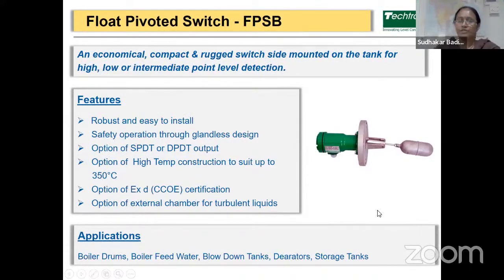The next one is a float pivoted switch. This is a single point switch, which is economical, compact, and rugged. It is side mounted to the tank for level detection at high, low, or intermediate level. This is robust and very easy to install through the flange or screw flange connection. The switching operation is safe through a glandless design. The switching output can be available as SPDT contacts or DPDT contacts. The option of high temperature construction is available, which suits up to 350 degrees Celsius. The option of X-proof enclosures, that is CCOE certified enclosures, is available. Again, the option of external chambers is available for turbulent liquids. Then applications are boiler drums, boiler feed waters, blowdown tanks, deaerators, and storage tanks.